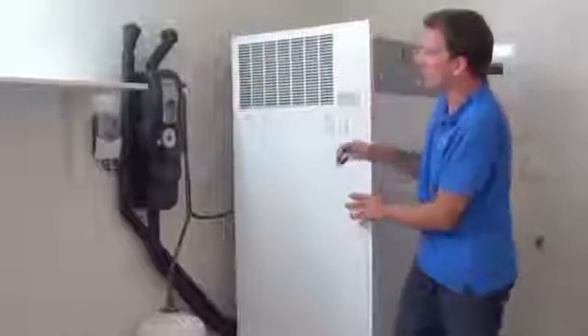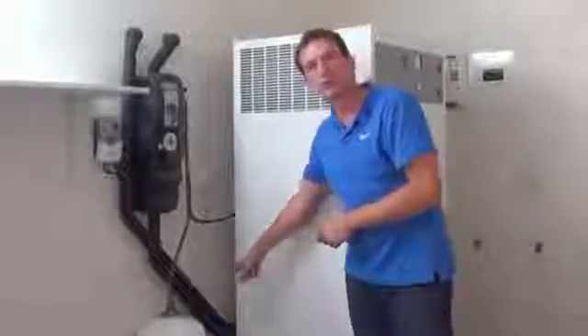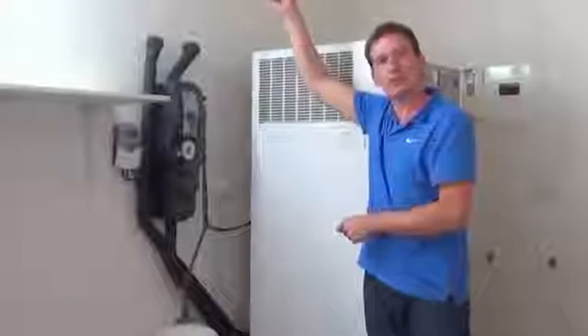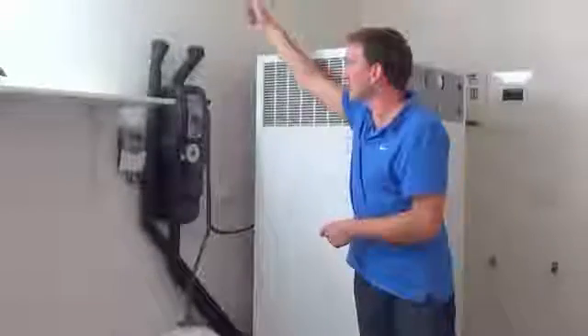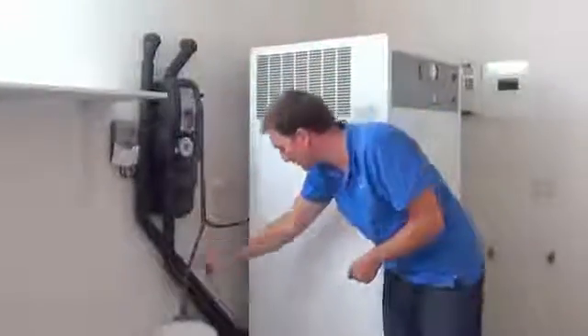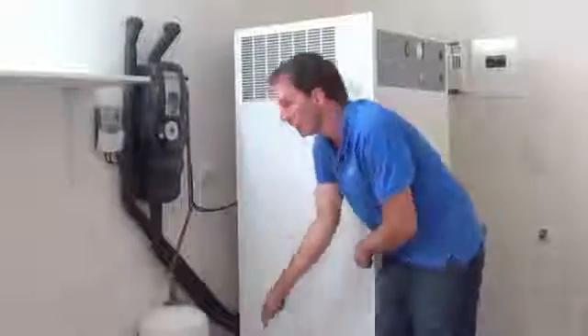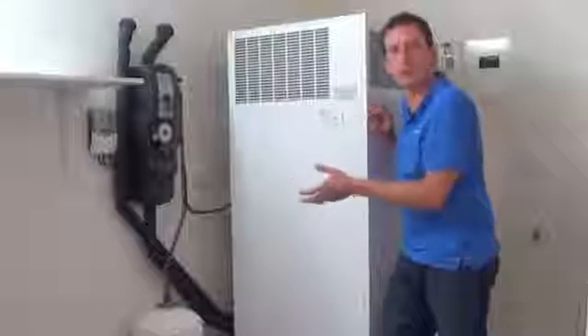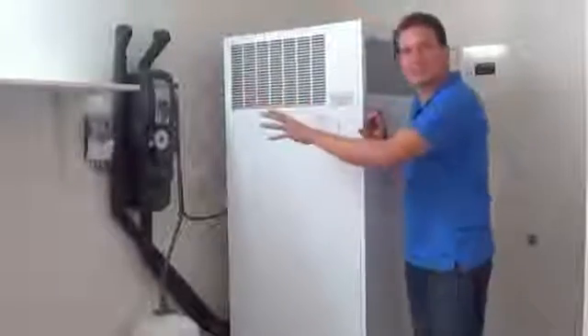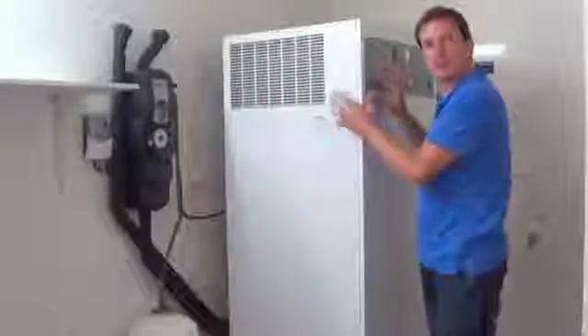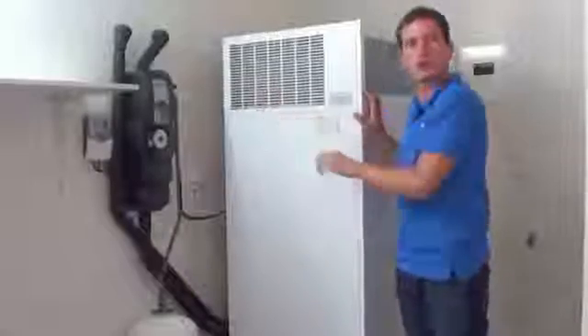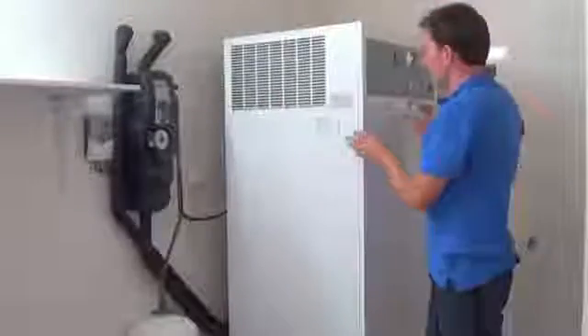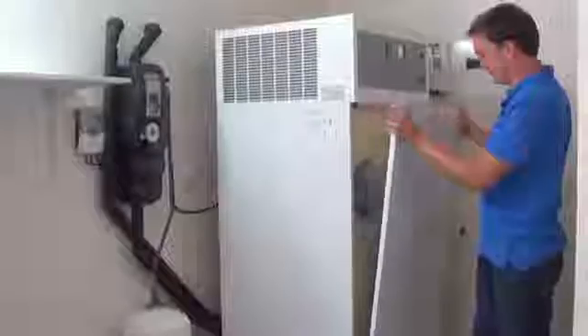Now what we're doing is, with a glycol system, we circulate glycol up to the panel. It absorbs the heat from the sun. The glycol brings that heat that it's absorbed and it pumps it into the bottom of the tank. Now, by doing this, we are marrying the two systems, but we are marrying it automatically. The solar system doesn't know what the heat pump system is doing, and the heat pump system doesn't know if the solar is actually kicking in. Let me show you how it's done.